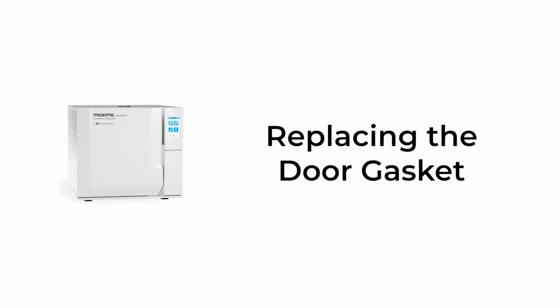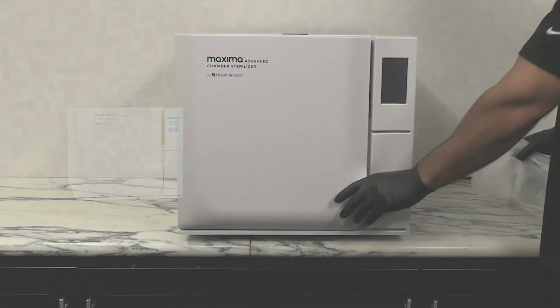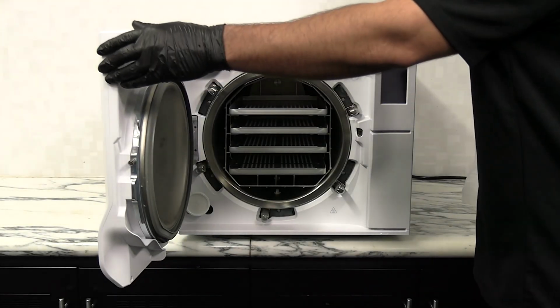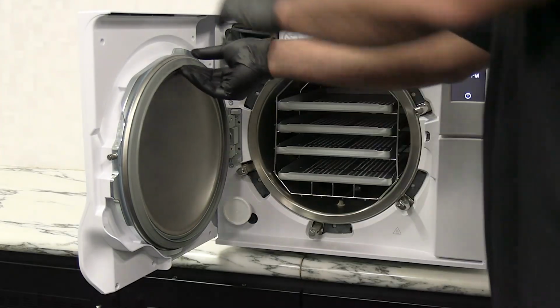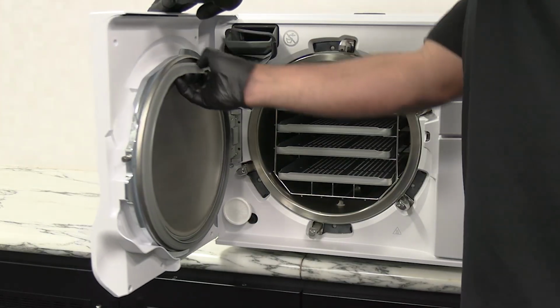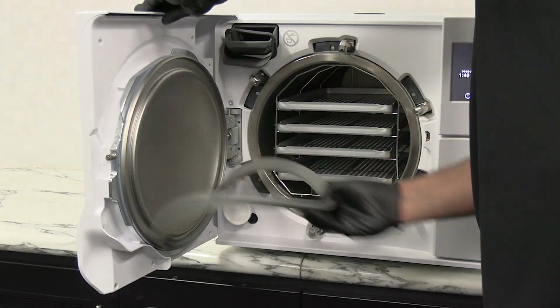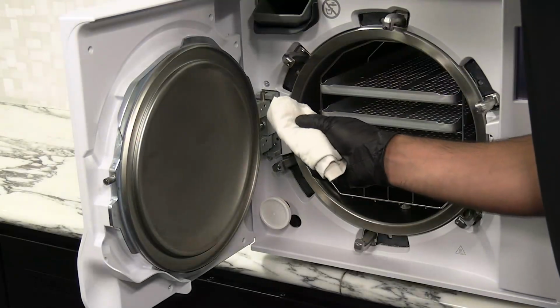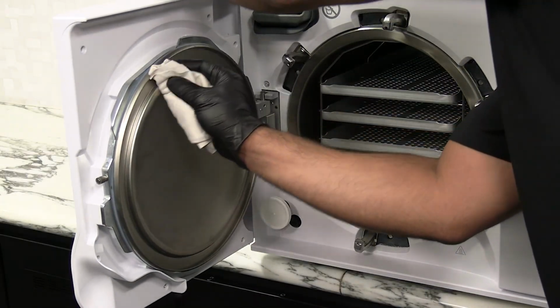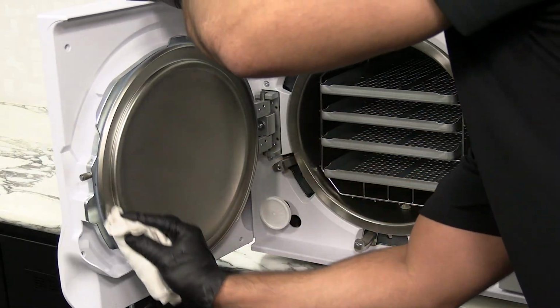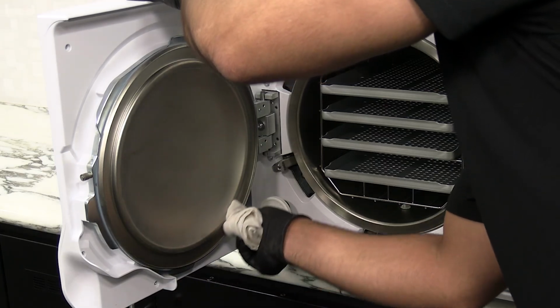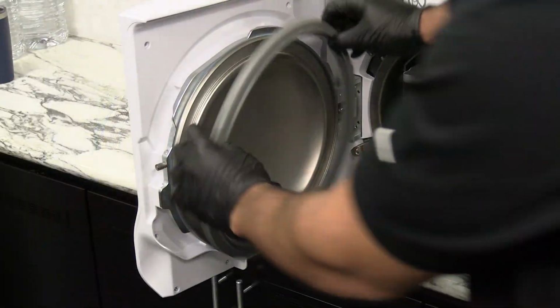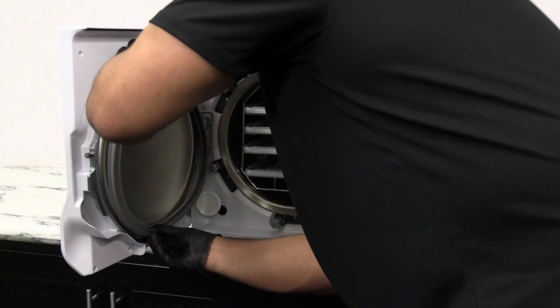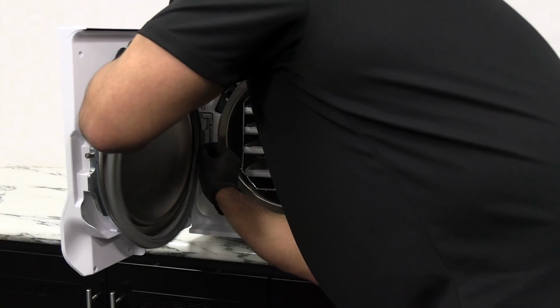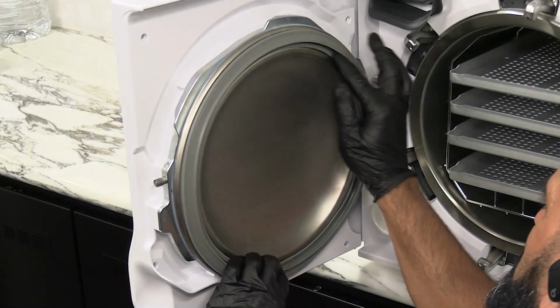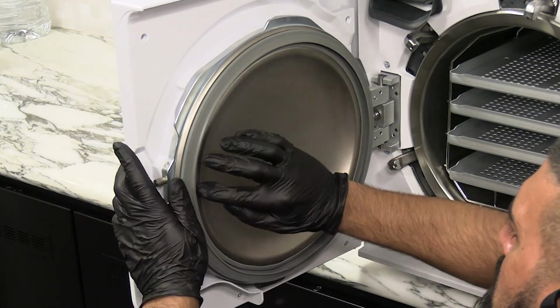Replacing the door gasket. Open the chamber door. Remove the used door gasket by hand. Carefully clean the seal seat and the inside face of the chamber door with a non-abrasive cloth moistened with clean water. Ensure no residue remains. Insert the new door gasket, pressing it in place evenly, first up and down, then left and right. Make sure the door gasket is seated evenly around the entire circumference.